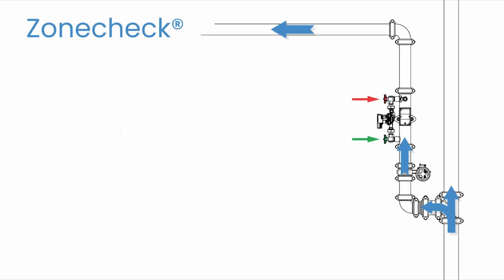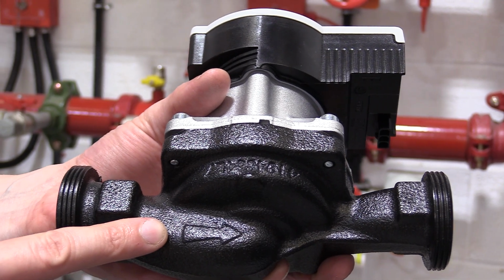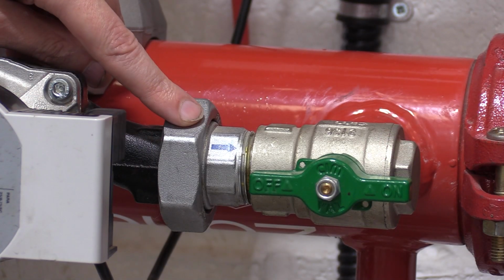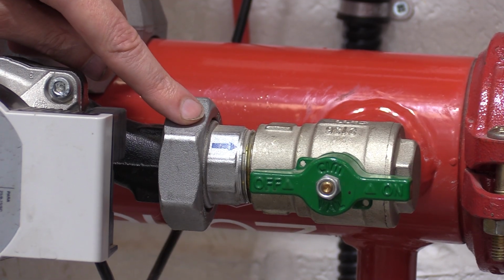If Zonecheck is installed vertically, please check that the flow of water in the pipework is up. The zone valve or stop valve should be upstream of the Zonecheck. The red valve should be above the green valve. The flow sticker on the Zonecheck manifold and the arrow on the flow switch should both be pointing upwards, in the direction of flow. The arrow on the pump casting and the non-return valve should both be pointing downwards.